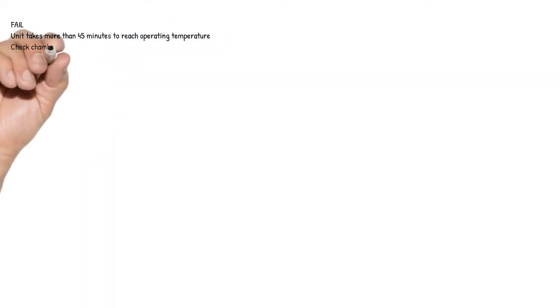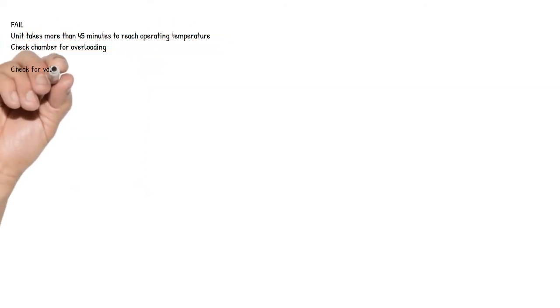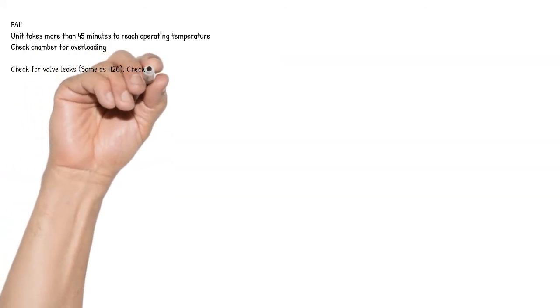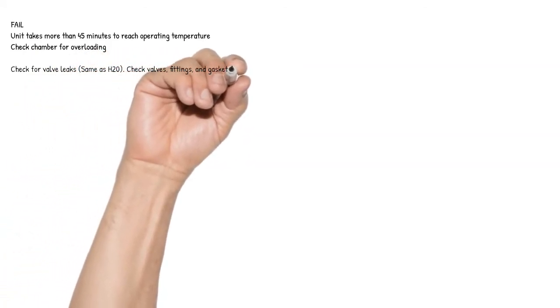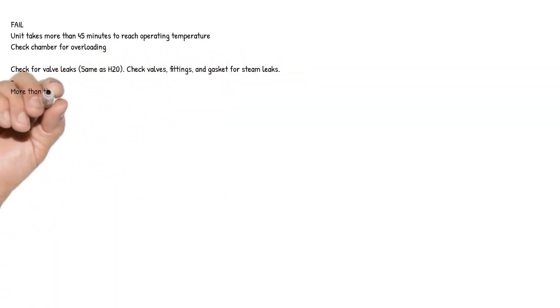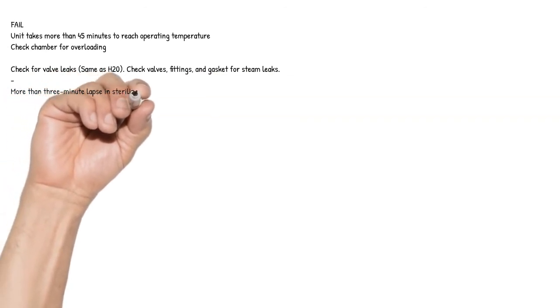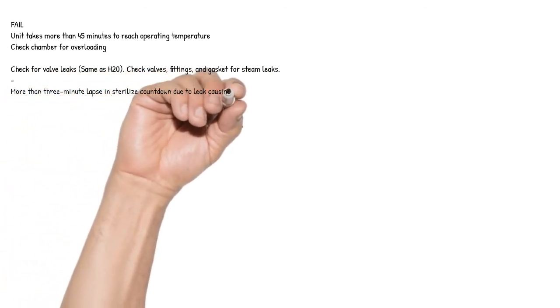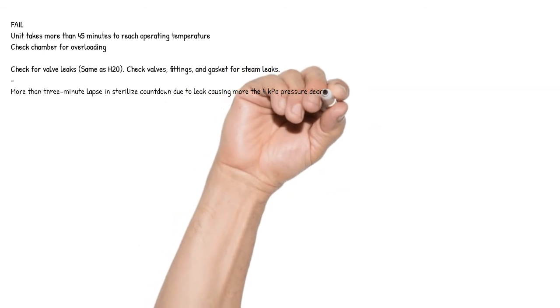Fail. Unit takes more than 45 minutes to reach operating temperature. Check chamber for overloading. Check for valve leaks, same as H2O. Check valves, fittings, and gasket for steam leaks. More than 3-minute lapse in sterilize countdown due to leak causing more than 4 kPa pressure decrease.